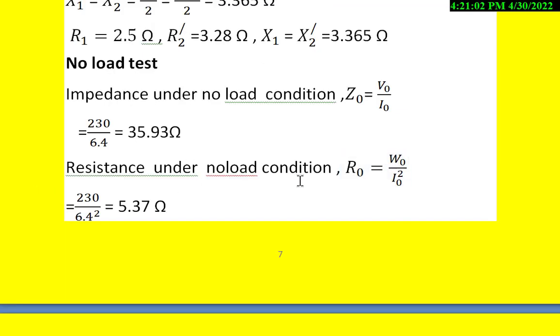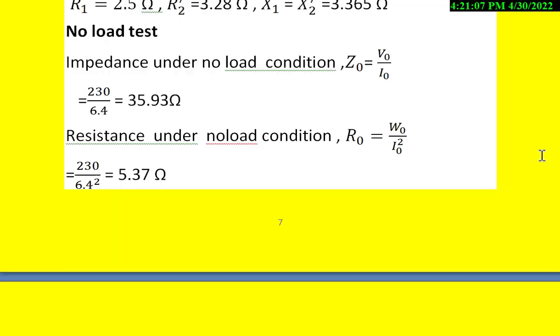Resistance under no-load condition: R0 = W0/I0². W0 = 220W and I0 = 6.4A. Therefore, R0 = 220/6.4² = 5.37Ω.